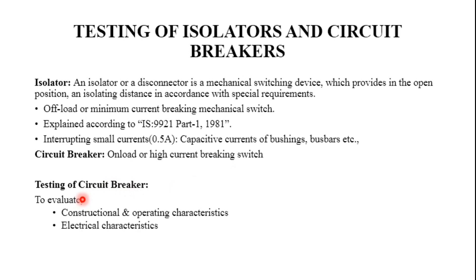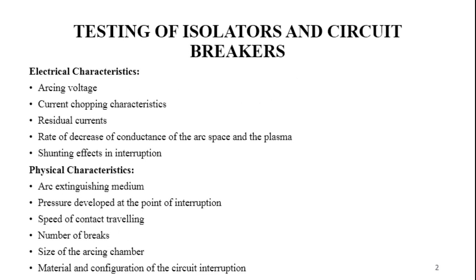For testing circuit breakers, there are two main categories: construction and operating characteristics, and electrical characteristics. The electrical characteristics to be determined include arcing voltage, current chopping characteristics, residual currents, rate of decrease of conductance of the arc space, and plasma shunting effects in the interruption process. A broad understanding of arcing voltage, residual current, and arc interruption is required.